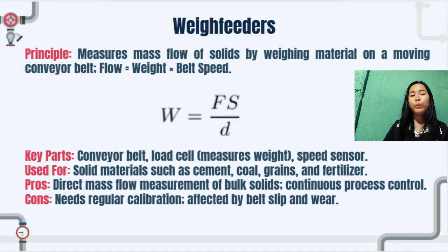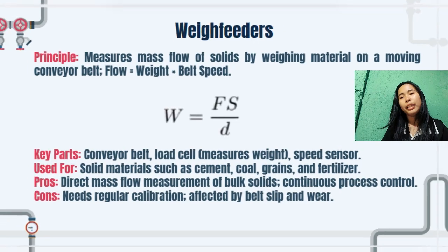It continuously weighs the materials on the belt using a load cell and measures the belt speed using a tachometer. The product of these two gives the mass flow rate of the solid materials. This method allows continuous measurement and control of solid materials in industries like cement, mining, and agriculture. However, it needs regular calibration, and belt wear or slippage can affect accuracy.